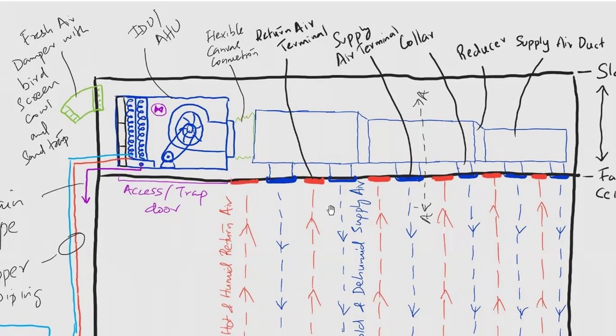And these return air terminals. So this orange color is meant to be the return air terminal, and it's not connected to any kind of duct. That means the existing return air, which has hot and humid characteristics, enters into the plenum area. All right. So that's how you collect the return air from each and every room. And later, you will terminate the return air at the backside of the machine itself. So we studied that in the indoor study, especially on the backside of the machine. We can see the air filters, especially 5 micron fine filters or bag filters.